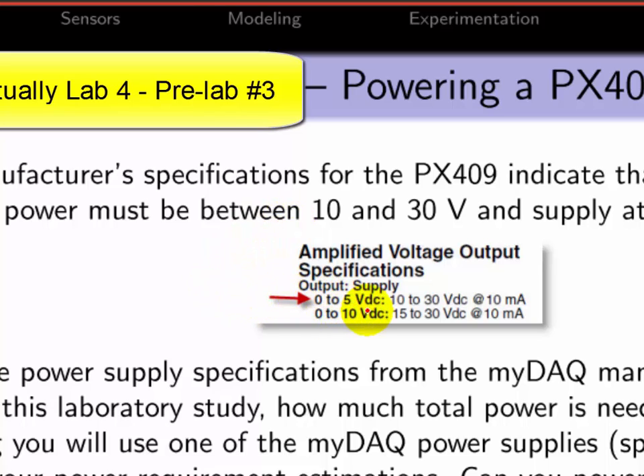This is a 0 to 5 volt DC output sensor. It requires excitation voltage and power — it's a powered sensor with amplified output. The nice thing is you don't have to worry about attaching any other signal conditioning; it has a clean DC output voltage you can connect directly to the MyDAQ, but you have to power it correctly.